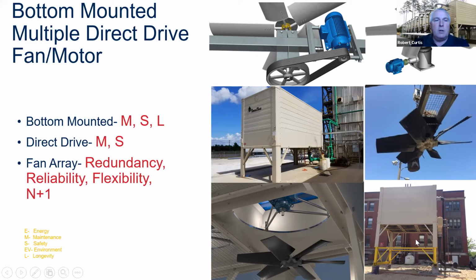And then the last item on this mechanical equipment, if you notice here to the right, we have a picture of a TowerTech tower, and you can see the 6 squares underneath there. Each square represents a motor and a fan. So TowerTech, instead of having a single motor, single fan, has a multiple direct drive system. So if you happen to lose one, you have redundancy. In this case, we have 5 of 6 running. If you lost one of these, you lost 100%. And so that gives you some reliability and redundancy, and also some flexibility in how you're going to operate your system. So when you look at our bottom-mounted multiple direct drive system, we really impact some of the concerns and questions people would ask about, can your cooling tower do such and such?